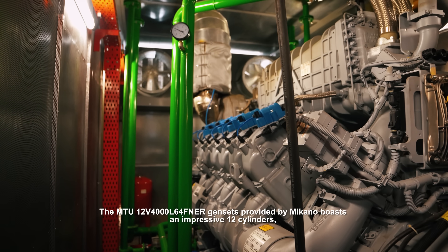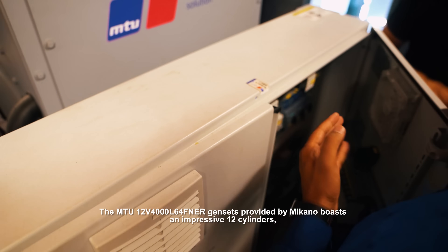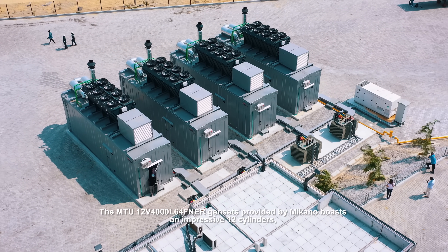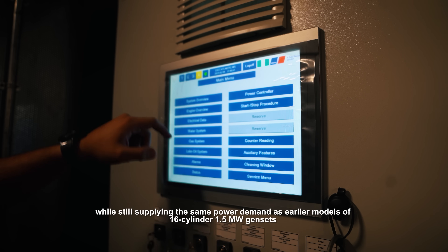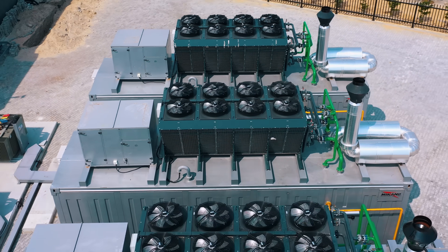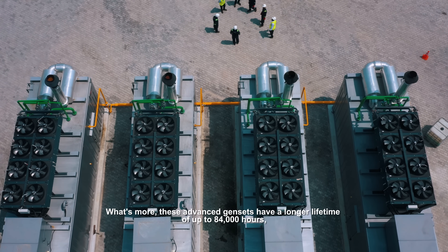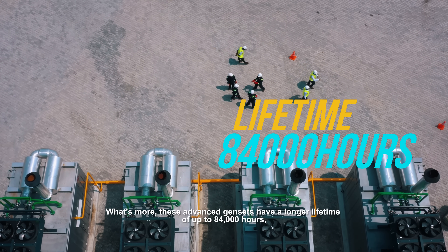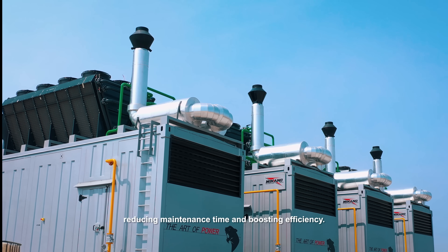The MTU 12-cylinder engine: the MTU 12V4000 L64 FNER gensets provided by Mikano boast an impressive 12 cylinders while supplying the same power demand as earlier models of 16-cylinder 1.5 MW gensets with a limited 64,000-hour lifetime. What's more, these advanced gensets have a longer lifetime of up to 84,000 hours, reducing maintenance time and boosting efficiency.